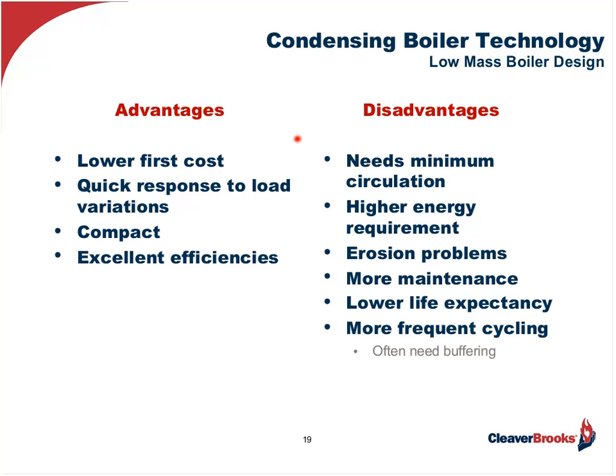The being able to respond to load quickly is a two-edged sword. They can respond too quickly, especially if there's no flow in there, and they will trip out on their operating limit. They will also have a higher energy requirement. It's not uncommon to see low mass boilers have pressure drops of 10, 15, 20, or 30 feet of head. That's pumping energy you have to spend 8,000 hours a year.